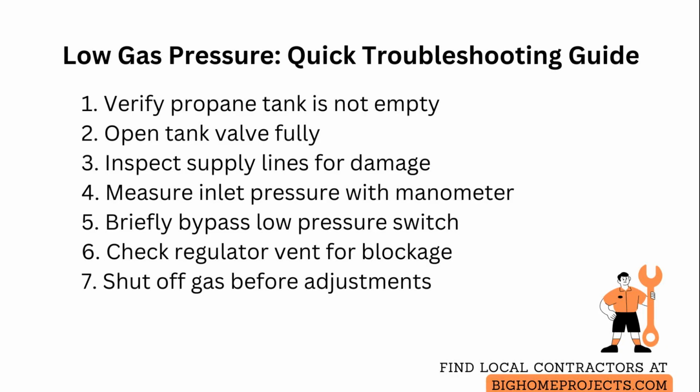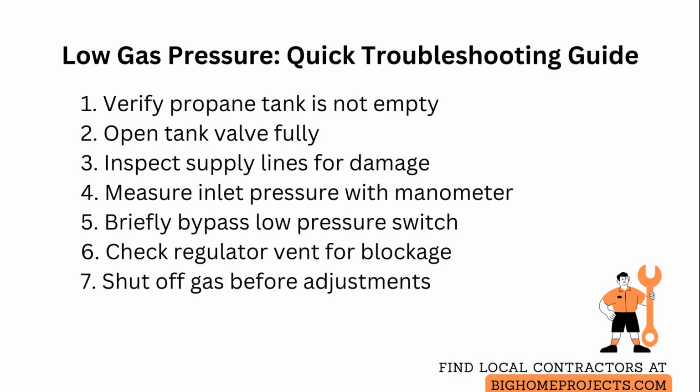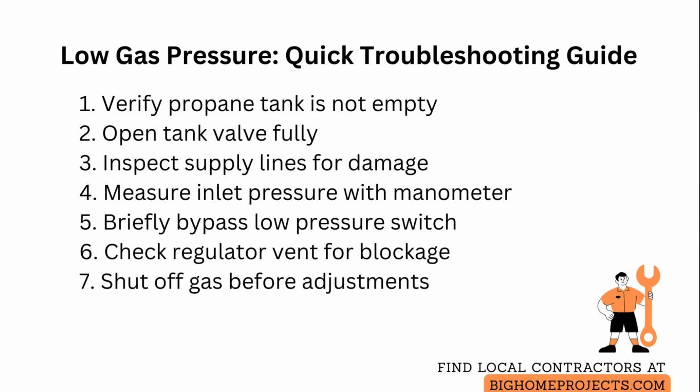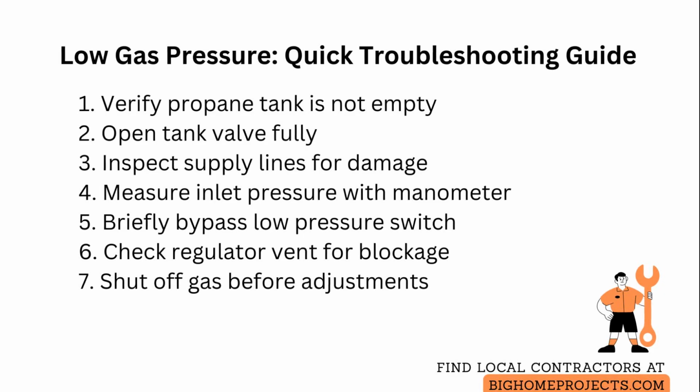If a low-pressure gas switch is installed, understand it is a safety device that interrupts blower or burner operation when pressure falls below a safe threshold, so temporarily bypassing the switch can help determine if the switch is the cause, but only bypass briefly for testing and restore it immediately.